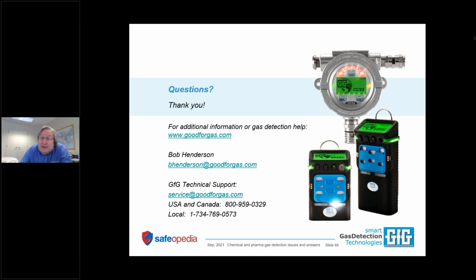So you're going to burn out sensors with methanol. With infrared, you don't have all of the filters that you have to go through. There's nothing that you can poison or burn out, and the sensor will respond very strongly and accurately to the alcohol if you've got the right sensor. The only thing that you always have to remember, if you have hydrogen, then you should consider adding a direct reading substance specific electrochemical hydrogen sensor to that multi-sensor instrument along with the IR LEL sensor.